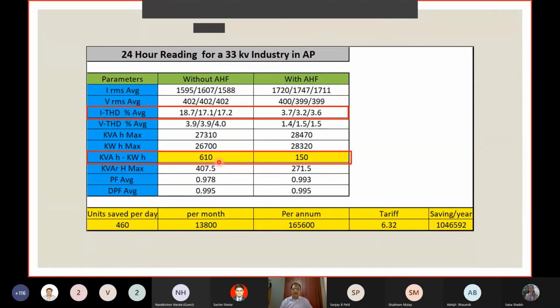This was based on a full day reading. I normally go to a site and connect a meter for a full day recording, with which I am able to do a variety of interpretation and recommendation. You have seen that today in my presentation, that in the hospital the 24-hour recording has been useful for a variety of interpretations like kVA, demand, power factor, harmonic factor, the voltage dip, and so on and so forth. So 4 or 5 varieties of power quality aspects can be presented using one single 24-hour window of data.